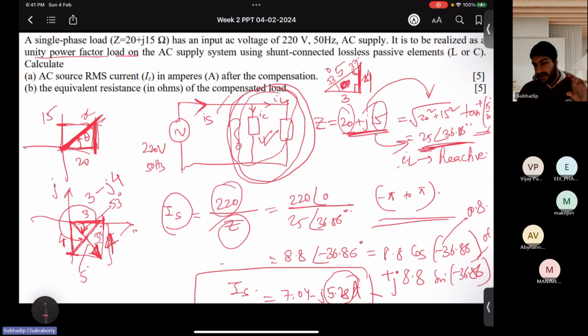Now, when you plug in a compensating element, what is the role of that? Only to compensate for this reactive current. So IS new is only the active component 7.04, because the other reactive component is compensated by the compensator. Just remember Kirchhoff's current rule, that this current is this current plus this current. So load current reactive component will be borne by the compensator, such that this current is in line with voltage. So 5.28 ampere, the reactive current, is the compensator current.